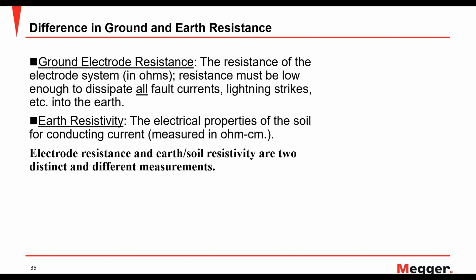And what is the difference between ground resistance and earth resistance? A lot of people confuse this. Ground electrode resistance is the resistance of the electrode system itself. It is usually in ohms, and it should be low enough to dissipate all kinds of fault currents, lightning strikes, etc. Whereas earth resistance or earth resistivity is the electrical property of the soil itself for conducting current, and it is measured in ohm centimeters. So anything that you see in ohm centimeters is the resistivity of the soil itself, and anything that you see in ohms is the ground electrode resistance. So something to keep in mind when you're looking at readings. This is a key indication that you have one or the other.